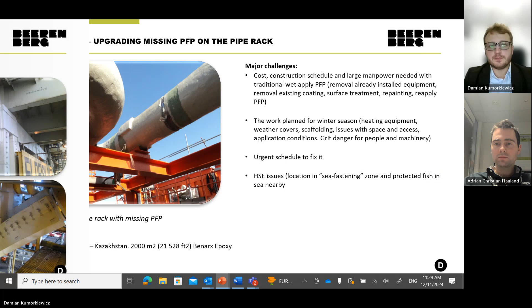Another case study is from Kazakhstan. The goal was upgrading missing passive fire protection on the pipe rack. Before commissioning, they discovered the pipe rack, fabricated in the Middle East, was missing the PFP application. The fabricator forgot to apply it, and the pipe rack was already delivered to site, fully erected, painted, and equipped with all surrounding equipment. They only discovered this afterward.